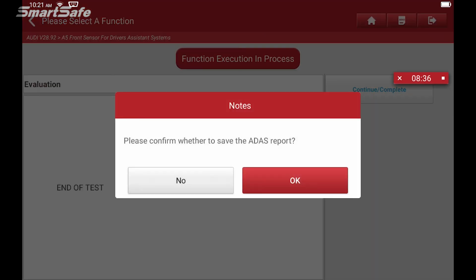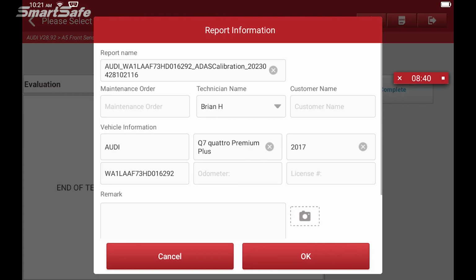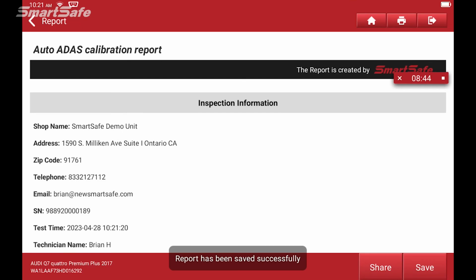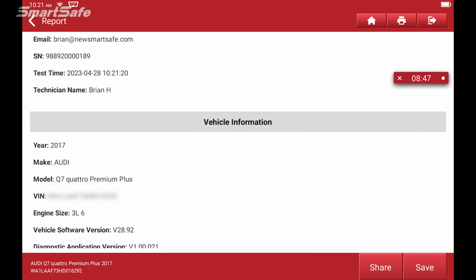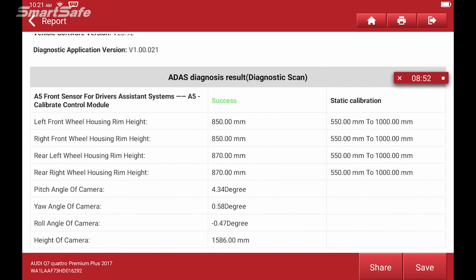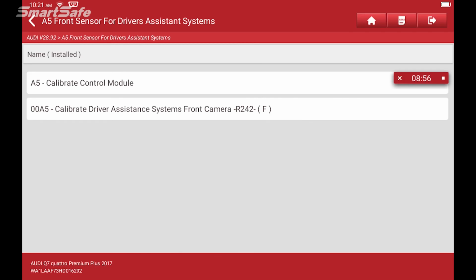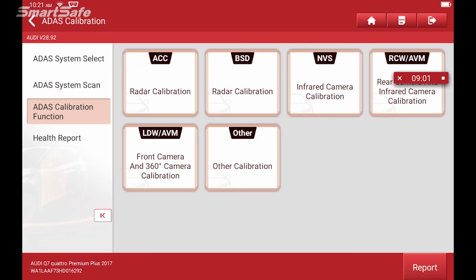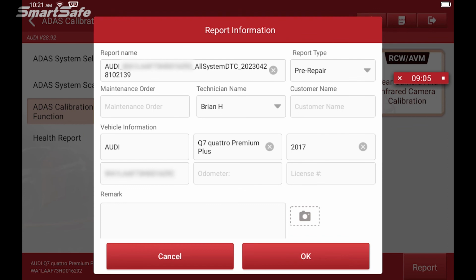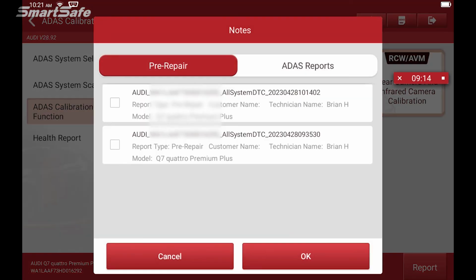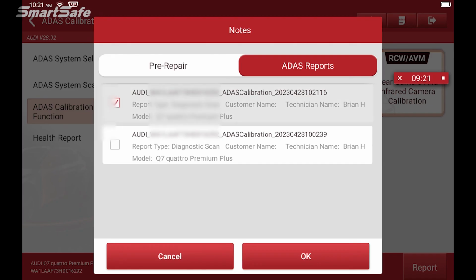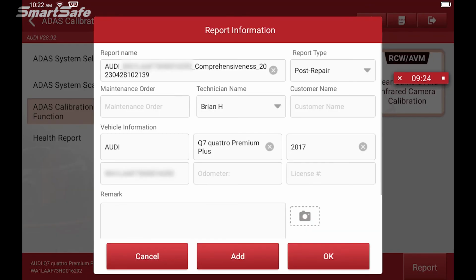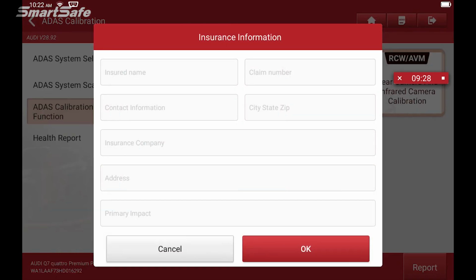Now we'll be prompted to complete our calibration report, so we'll hit OK. And in our calibration report, we show a successful calibration. We'll hit save. And next we want to combine our reports, so we'll hit the report button. We'll change our report type from pre-repair to post-repair. We'll then click on the add button, and we'll combine our pre-repair report along with our diagnostic scan to complete a comprehensive completion report. We'll hit OK. If this was an insurance claim, you can go ahead and enter the insurance information at this time. But in this case, we'll hit OK.